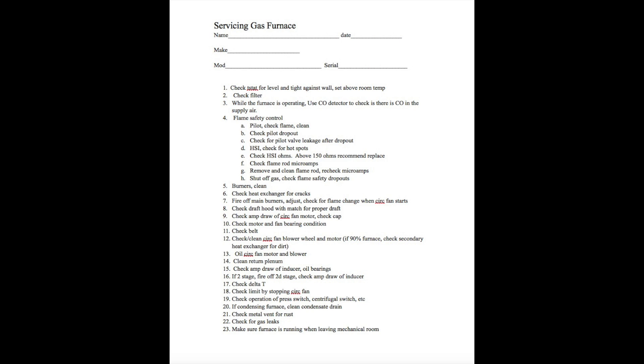You're going to check the pilot dropout. Now what is a pilot dropout? The pilot dropout is on the old pilot furnaces. If the pilot blew out within three minutes, the unit had to shut down. It had to shut all gas off to the appliance. That's a pilot safety. So you're going to blow the pilot out and wait for the click. Once it clicks, try to relight the pilot with a match. If the pilot does relight, you've got a gas valve problem. So the gas valve is going to need to be replaced.